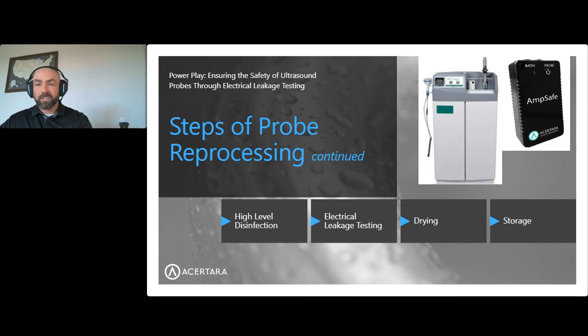If it doesn't, stop. Don't proceed. You have to go get the biomed involved, because if you proceed with the high-level disinfecting after you have found a probe does not pass electric leakage testing, the likelihood that you're going to destroy that probe is much, much higher.